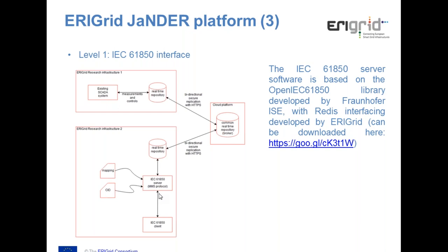In this way, it is possible to have a 61850 interface between different facilities by using a standard MMS communication without any security problem, of course, because the actual MMS communication is local to only one research infrastructure. Then the remote, the internet transmission of this data is handled by the virtual bus. So this is a way to decouple the deployment of 61850 from the problem of having a wide area information exchange between research infrastructures.